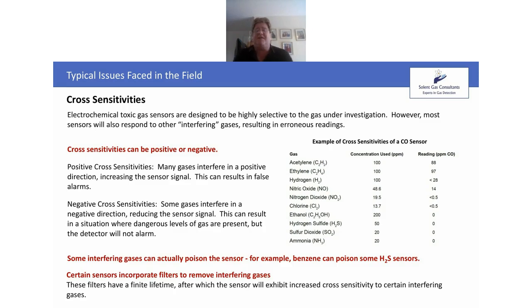Right, cross sensitivity. So this is one of the main problems faced in the field. These sensors are designed to be as selective as possible to detect just the target gas, but in practice that's very difficult to do, and they will respond to other gases in the field. So this cross sensitivity can be positive or negative. For positive cross sensitivities, if you have some interfering gases, then you would get an increase in the sensor signal, so potentially you would get false alarms, which can be costly.